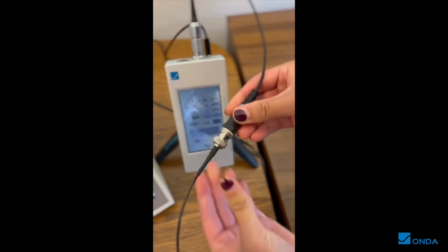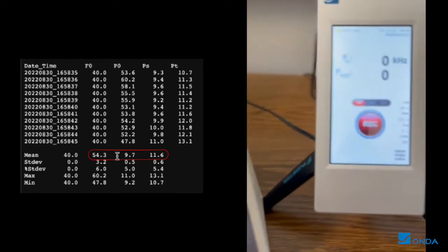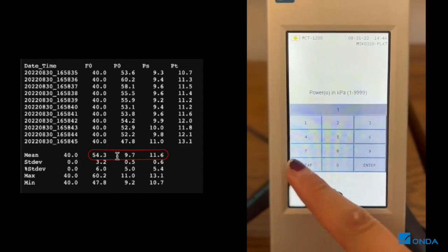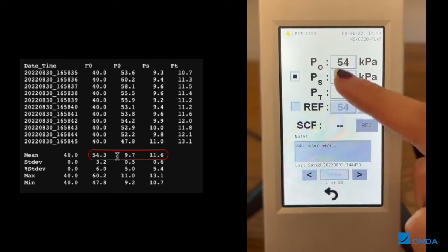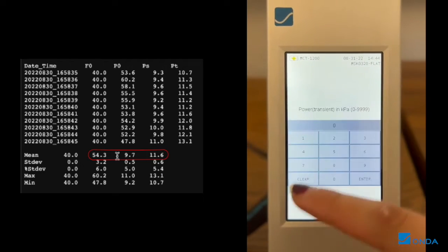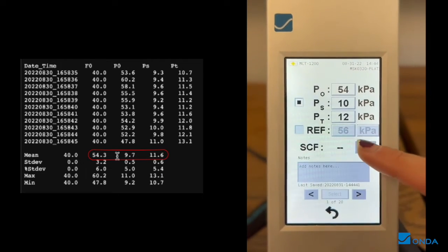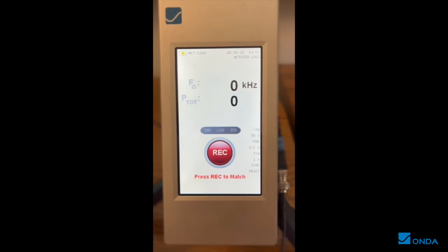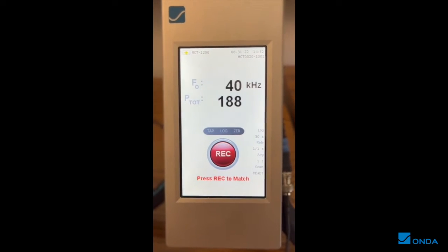Connect the CMS to the MCT1200. Note the average values and input these reference values into the MCT1200. Press Record to generate a Scale Factor.